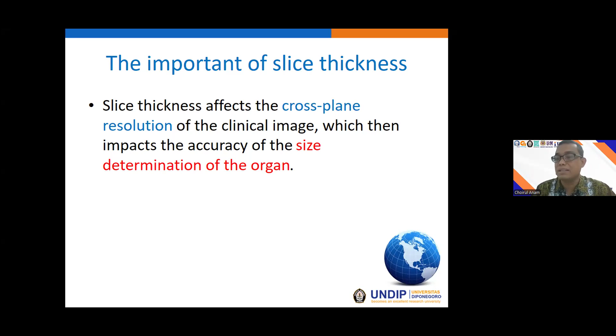This is a study done by Prionas and published in the Journal of Applied Clinical Medical Physics, JACMP, and they assessed the dependency between the slice thickness and volume accuracy. And we can see here, based on the graph, it is clearly seen that as the slice thickness becomes smaller, the accuracy of the volume is higher. Okay, so if we want a more accurate volume definition, we should use a smaller slice thickness. But I already said that the image will be noisy.